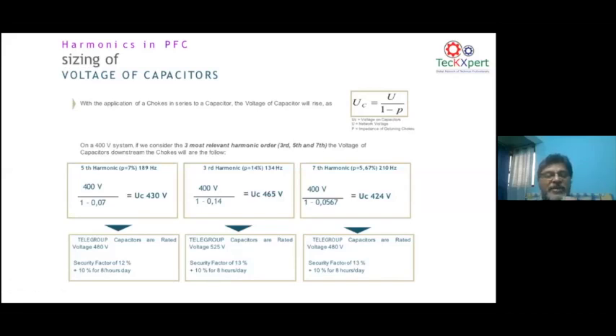Because if you use a 7% detuned reactor, the capacitor voltage goes up almost by 10% because it is a vectorial sum. When you put a reactor in series with a capacitance, at the capacitor terminal, the vector sum is that the voltage goes up. Now, in a 7% reactor, you will have somewhere about a 7% rise in voltage. So, if you're using a 400 volt network, you have to make sure your capacitor bank is somewhere around 440 volt. Similarly, if you're using a 14% reactor, you have to make sure that your capacitor is somewhere about 480 volts.